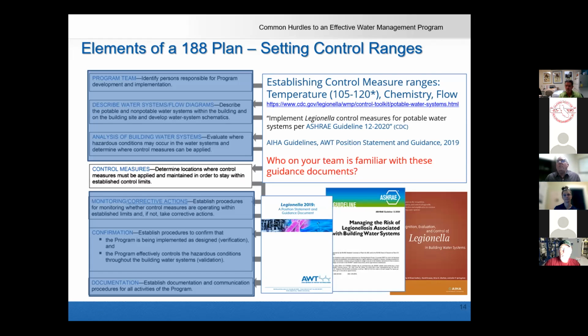The example you bring up of difficult temperatures is a common problem we face, and that's when you go back and look at your response actions. If we've got a high-risk area where something goes out of range, or we can't keep it in range, maybe we implement a response action where we hyperheat those fixtures every Thursday or something—I'm making that example up, but we have to look at what's feasible and what works. If we've got a certain bacterial load in that fixture, does hyperheating it on a regular schedule keep that bacteria managed? You've got to find the sweet spot of doing the right testing at the right locations to determine if your response actions are managing the problem in your system.